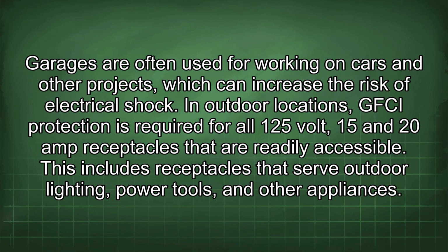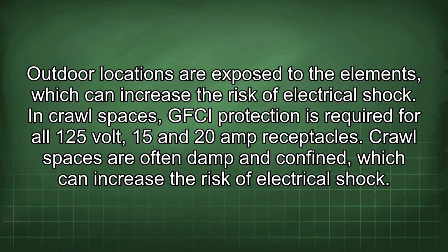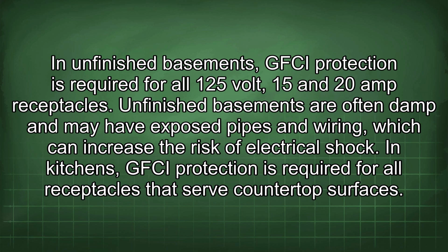In outdoor locations, GFCI protection is required for all 125-volt, 15 and 20 amp receptacles that are readily accessible. This includes receptacles that serve outdoor lighting, power tools, and other appliances. Outdoor locations are exposed to the elements, which can increase the risk of electrical shock. In crawl spaces, GFCI protection is required for all 125-volt, 15 and 20 amp receptacles. Crawl spaces are often damp and confined, which can increase the risk of electrical shock. In unfinished basements, GFCI protection is required for all 125-volt, 15 and 20 amp receptacles. Unfinished basements are often damp and may have exposed pipes and wiring, which can increase the risk of electrical shock.